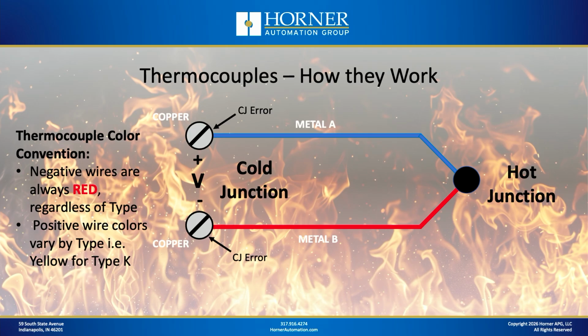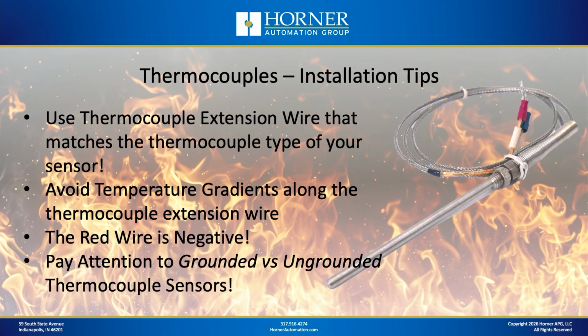Now, in terms of wire convention with thermocouples, as the previous chart may have shown, and you may have noticed, there's lots of different color codes for different types of thermocouples, but the one thing that is pretty much universal is that the negative lead from a thermocouple probe will be red. That's critical, okay? If you don't remember anything else from this presentation, remember that the negative lead is red with thermocouples, because if you connect that backwards, you're going to end up with definitely inaccurate results for sure.